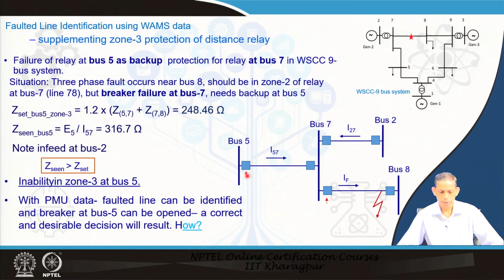So, that will continue. The inability of zone 3 at bus 5 leads to a dangerous situation. With PMU data we can identify the faulted line, and if the breaker at bus 5 can be opened from an independent protection arrangement that can supplement the available protection schemes, then it will be better. Now, the question is how that can be implemented.